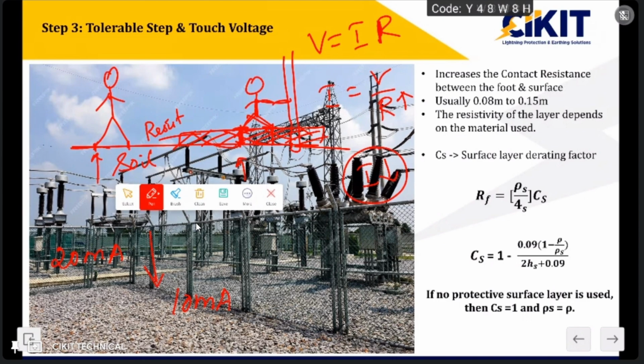So, by introducing this highly resistive layer, we are bringing down the value of current that might be flowing through the body, and hence we are reducing the impact and can ensure the safety of the person. The ultimate aim of providing this highly resistive layer is to increase the contact resistance between the foot and the surface. In general, we provide this layer with a thickness of 0.08 meter to 0.15 meter, which is almost 150 mm. Since we are introducing this layer, the resistance seen by the human body is increasing, and hence we introduce a factor called Cs, the surface layer derating factor, and include this value Cs in the calculation.